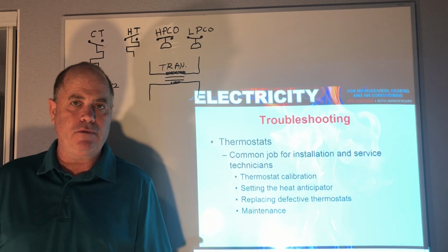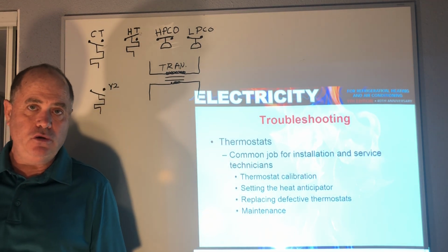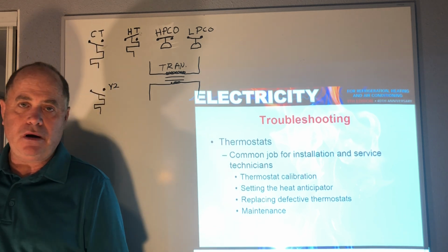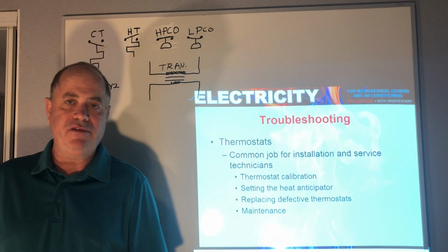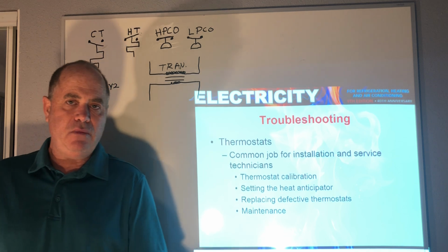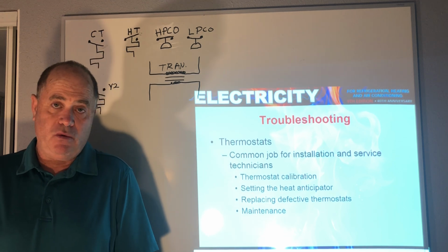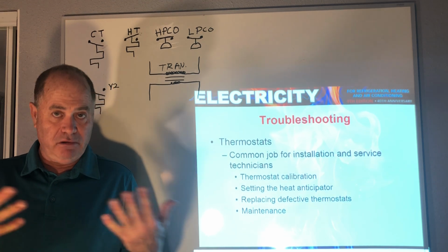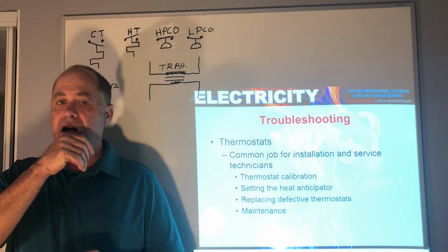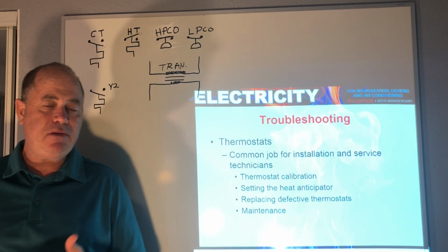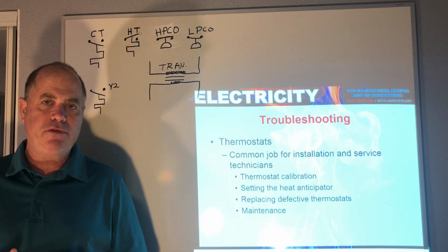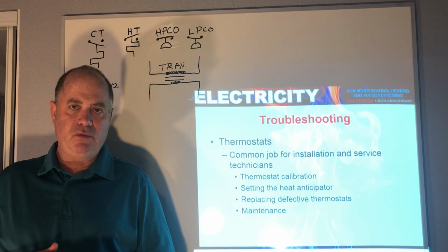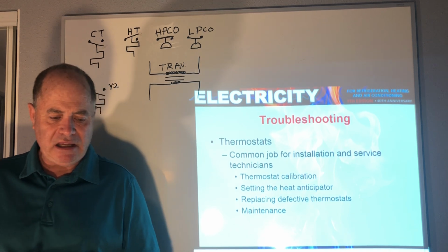If it's getting 24 volts and you have a call for cooling, but it's not letting the 24 volts out, let's say on the Y terminal of an air conditioning thermostat, then we can say that the thermostat itself is not working, and we can replace the thermostat. Likewise with heating, if it's not giving power to the W terminal on a call for heating, then we would think that we probably need to replace that thermostat.